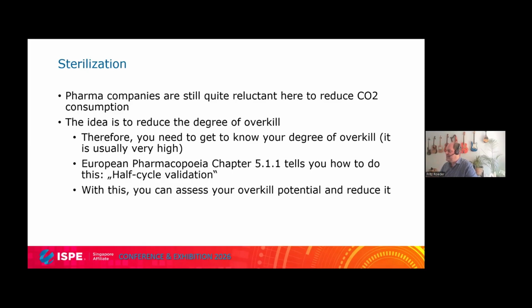Celsius. This is the basic requirement. But what we do typically is we apply a lot more heat, a lot more enthalpy on the sterilizing goods than we need. And this 15 at 121 already includes some overkill. But people do a lot more. And also, if you use dry heat sterilization, it's the same. There are the so-called F values, the lethality values that are being calculated, and they are far beyond.